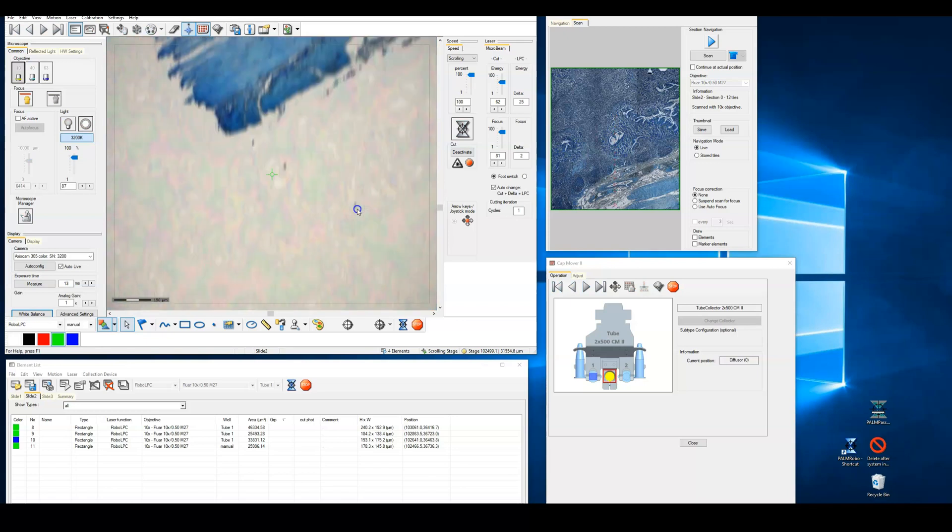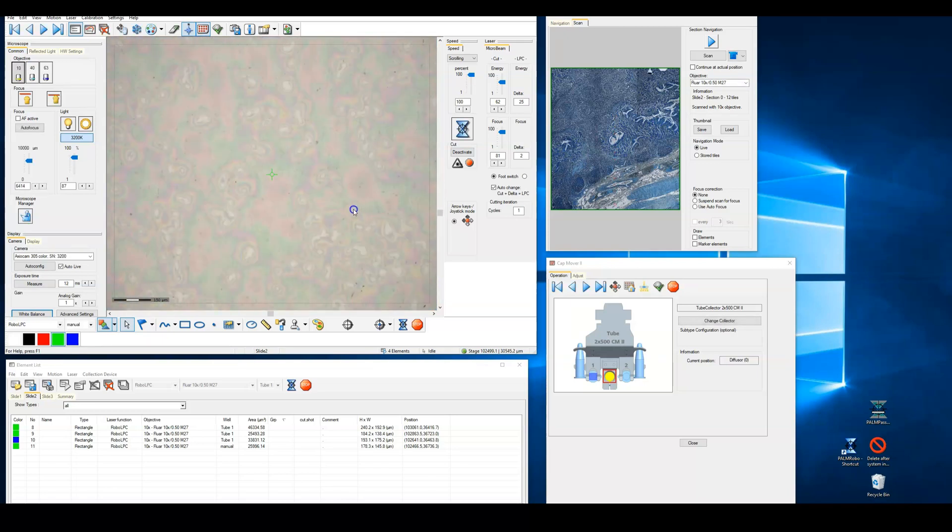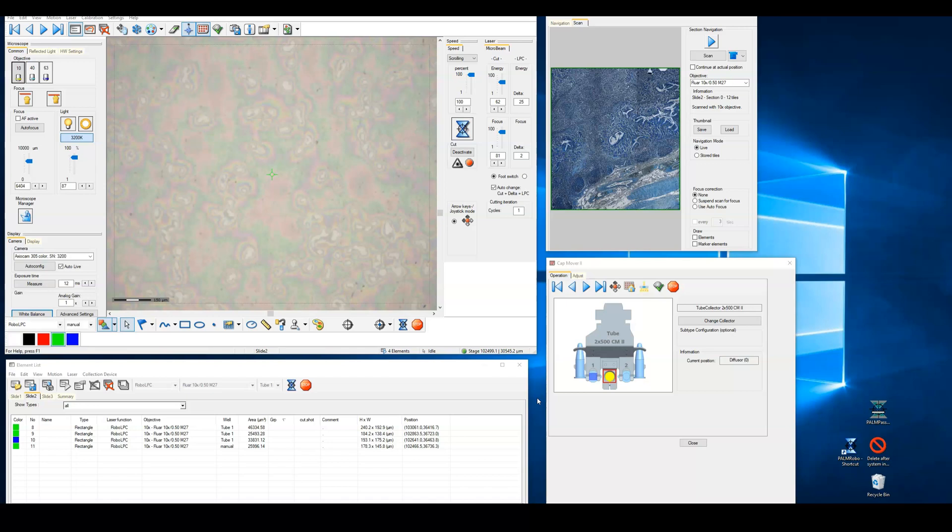I'm going to use the joystick to navigate to a region of the slide that does not have any sample to discuss how to optimize the laser micro dissection. In order to check the focus and power of the cut laser, when you're just learning to use the LCM, it's best to practice on a membrane slide without any sample. As mentioned previously, several samples shipped with the LCM system, and one of the membrane slides should last for the testing purposes for the life of the instrument. Membrane slides can be identified by having a rectangular region covering the majority of the slide that is semi-transparent. The slide we have now is one of those samples, so I'll navigate away from the sample to an area of the membrane that is blank. You should still be able to see what appear to be small pores in the membrane.